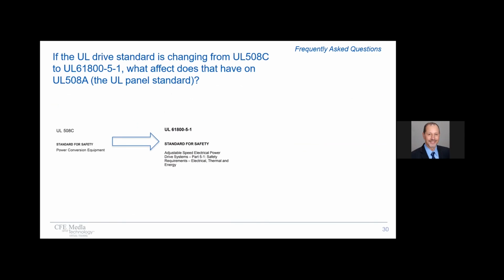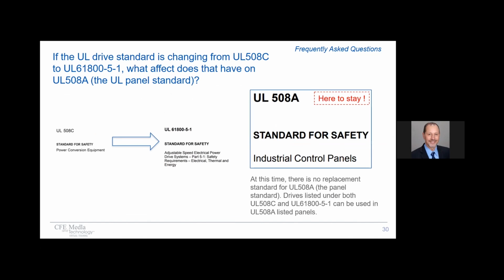Next question. If the drive UL standard is changing from the old standard 508C to the new standard 5-1, what effect does that have on UL 508A, which is the panel standard? Well, 508A, not to be confused with 508C, is the standard for industrial control panels, and it is here to stay. At this time, there is no replacement for the panel standard 508A. So drives listed under both the old standard and the new standard can be used in 508A listed panels.